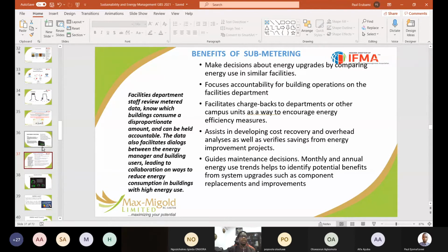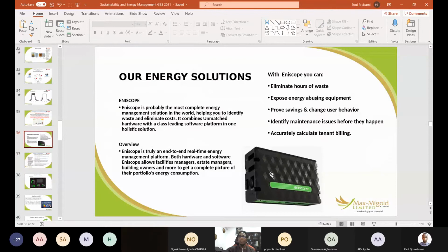This Eniscope device is capable of metering 24 circuits, 24 channels single phase, or 8 channels 3 phase. This means I can have one in my panel room where my incoming power, my generator outputs, and my power distribution into the various buildings or floors are captured. I take all of those three-phase distributions and meter all of them with one of these.